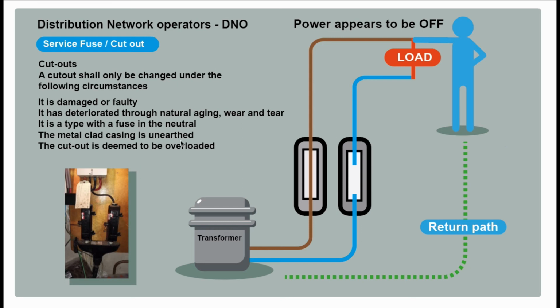But just a quick word on the fuse neutral and why that's dangerous. Here we have the service cutout with the fuse in the line and in the neutral, and for whatever reason this neutral fuse is blown, so that means you've got no return path back to the transformer. It will appear like all the power is off in the installation. So when you go to do your testing and looking around seeing what's going on, you might be in danger of coming in contact with the live line wire, especially if you're thinking everything's off. So you've got to be super careful.